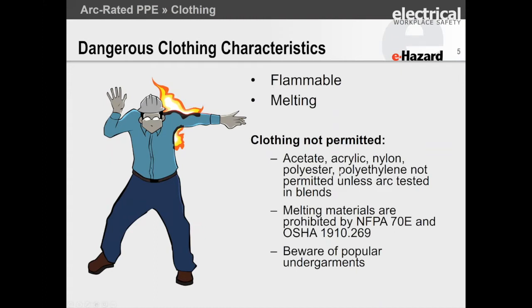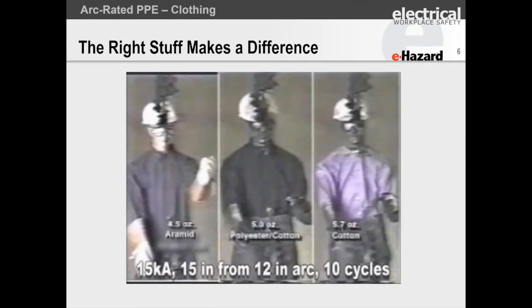It excludes acetate, acrylic, nylon, polyester, polyethylene. Any materials that melt you don't want unless they're arc rated and in a blend. You can blend in some polyester or polyethylene, and there's one brand new material that's 100% polyester but non-melting. It's really new, but expensive. If it's cheap, it's probably not what you want, so beware and watch out for melting undergarments.